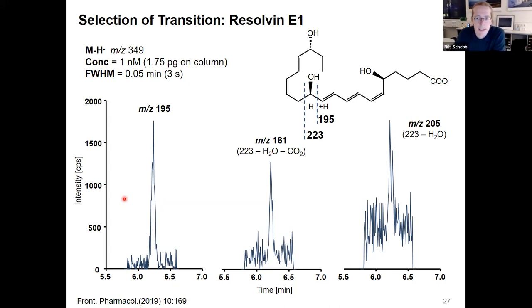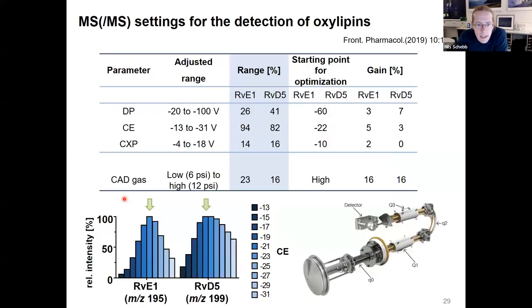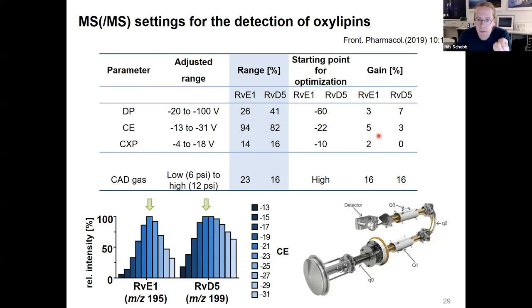Once you have selected these transitions, it's important to set up the mass spec so that transitions are detected with high sensitivity. For this, it's important to adjust the electronic parameters of the instrument. For example, the collision energy — if you choose a completely wrong value, you don't have any sensitivity at all. However, if you have a good starting point, such as minus 22 on the instrument, the optimization yields only a little better signal, because oxylipins behave more or less similarly with respect to electronic parameters in the triple quadrupole mass spectrometer.